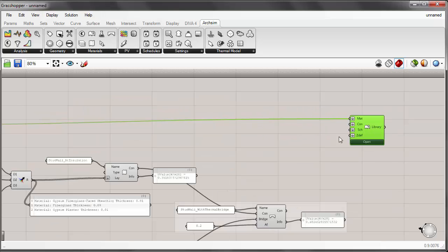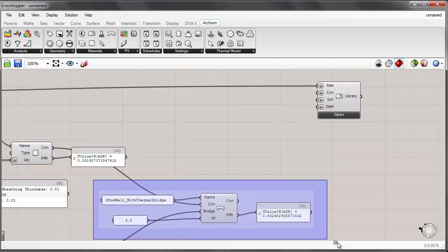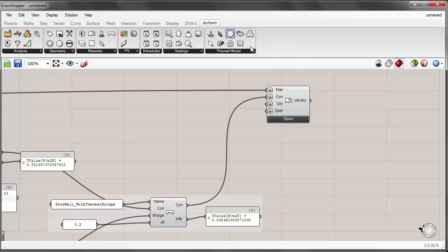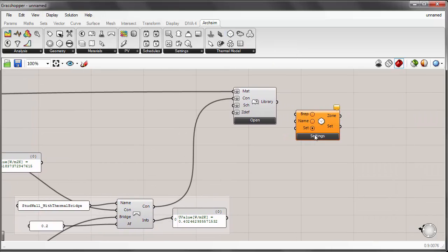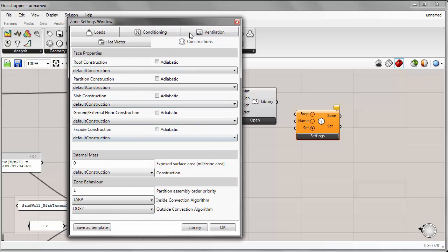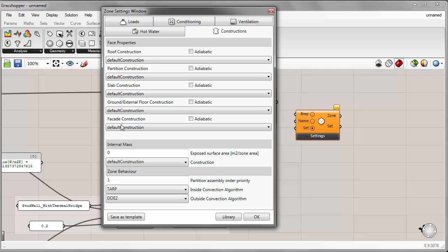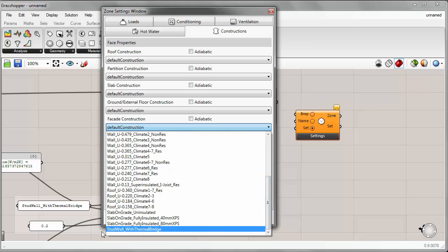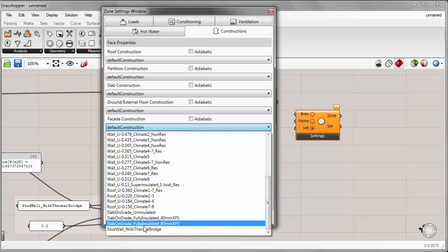I'll give this construction assembly the name stud wall with thermal bridge and plug that into the name input. Comparing the overall effective U-value to before, we can see that considering the 20% framing factor for the wood, we now have an effective U value of 0.4 instead of 0.35. To input this construction into our library, we connect the construction output into the construction input of the library component. Then in the thermal zone settings under constructions, the stud wall with thermal bridge now appears in the list.